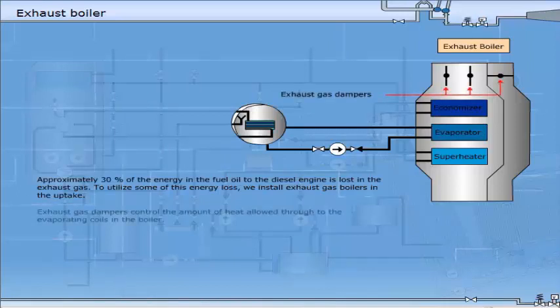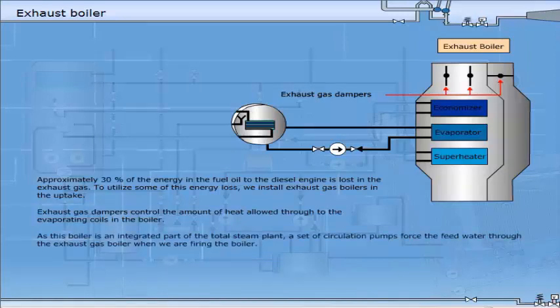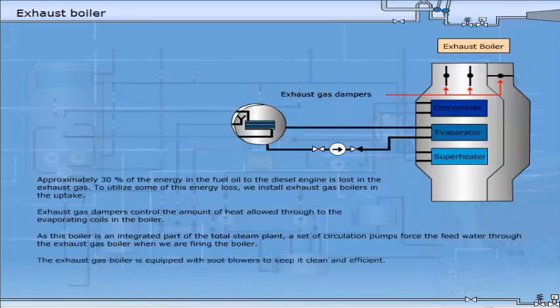Exhaust gas dampers control the amount of heat allowed through to the evaporating coils in the boiler. As this boiler is an integrated part of the total steam plant, a set of circulation pumps force the feed water through the exhaust gas boiler when we are firing the boiler. The exhaust gas boiler is equipped with soot blowers to keep it clean and efficient.